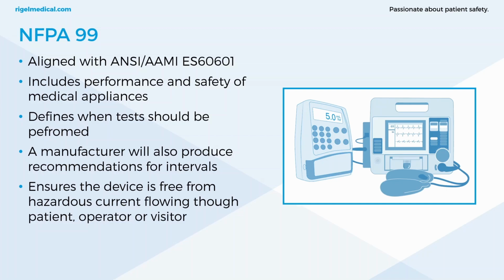Now in this webinar we're going to talk about the electrical safety tests specifically. So we are going to focus primarily on the equipment under test, whether it's fixed or portable. So each manufacturer typically produces a PM procedure for their equipment, and they will recommend intervals for testing. Now in previous revisions of NFPA 99, there were statements of 6 months in critical areas and at least every 12 months for general medical equipment. Now these statements seem to be phased out in most recent revisions, but the risk is still present. So best practice, at least every 12 months for testing medical devices. The risk there is still present, should be carried out regularly. Just ensures that the device is free from any hazards.